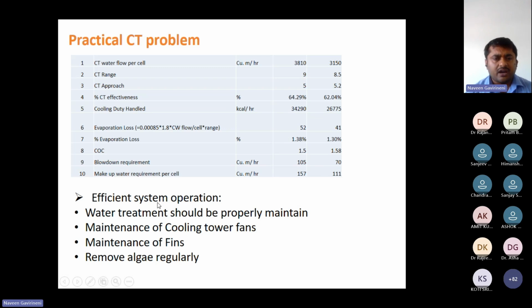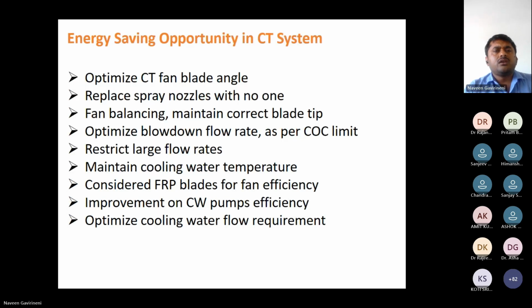I have given the efficient operation of the system here. Water treatment should be maintained. Maintain the cooling tower fan by removing all the algae, and maintain the fins also. These are the energy saving opportunities in the CT system. Optimize CT fan blade angle. Replace spray nozzle with a new one. Sorry, this is the new one.